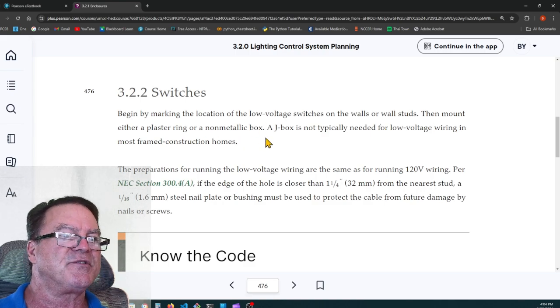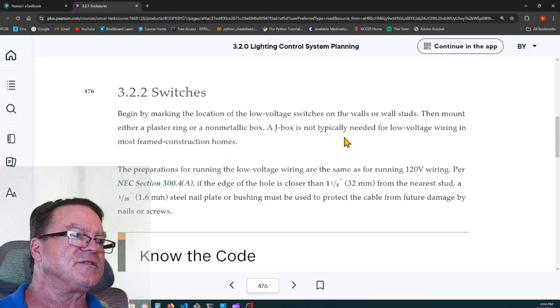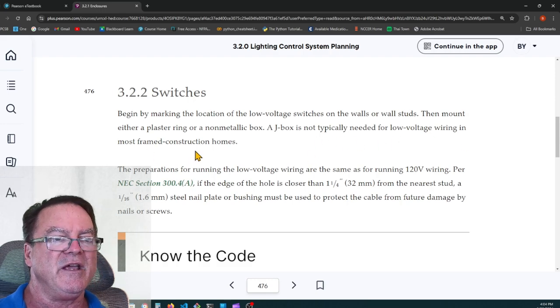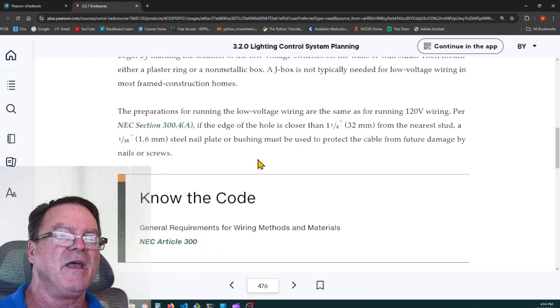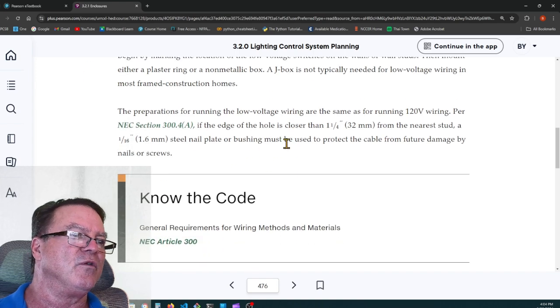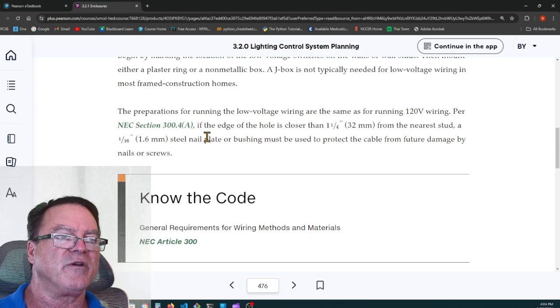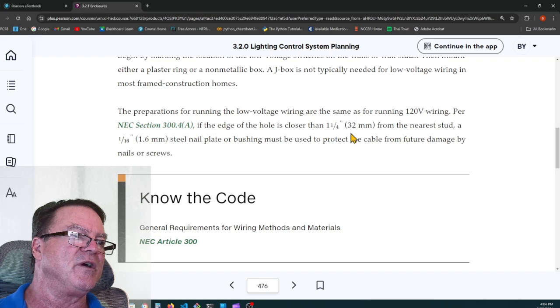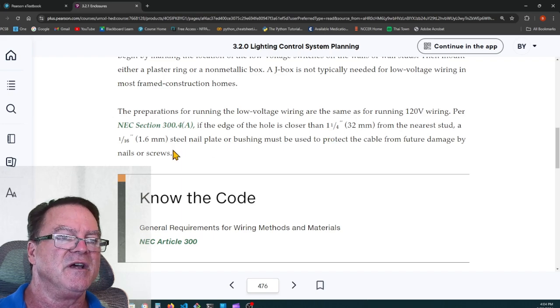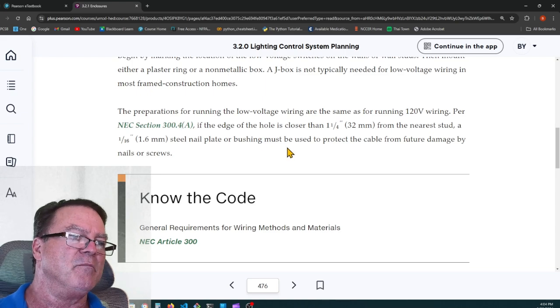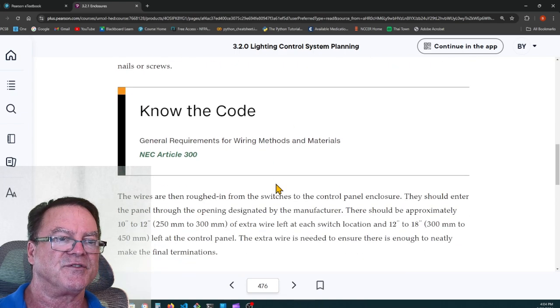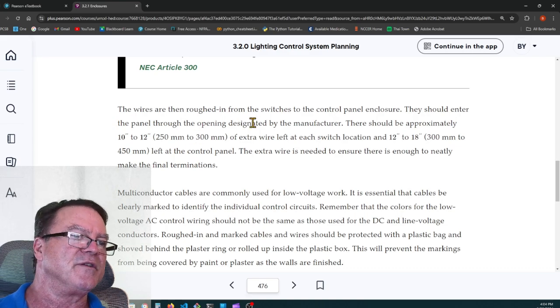Switches. Begin by marking the location of the low voltage switches on the walls or studs. Then mount either a plaster ring or a non-metallic box. A J box is not typically needed for low voltage wiring in most framed construction homes. Preparation for running the low voltage wiring is the same as for running the 120 volt wiring per NEC section 300.4(A). If the edge of the hole is closer than 1.25 inches from the nearest stud, a 1/16 inch steel nail plate or bushing must be used to protect the cable from future damage by nails or screws.